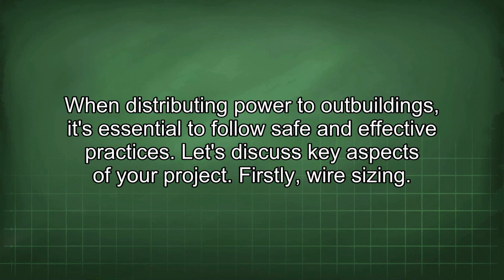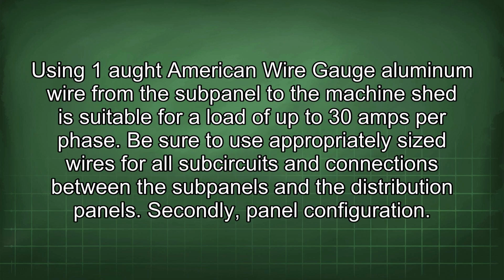When distributing power to outbuildings, it's essential to follow safe and effective practices. Let's discuss key aspects of your project. Firstly, wire sizing. Using 1/0 American wire gauge aluminum wire from the subpanel to the machine shed is suitable for a load of up to 30 amps per phase. Be sure to use appropriately sized wires for all subcircuits and connections between the subpanels and the distribution panels.